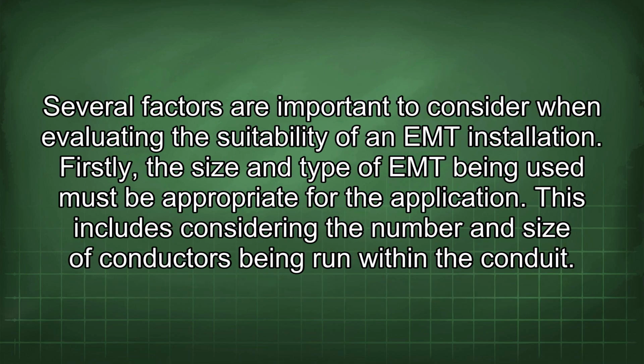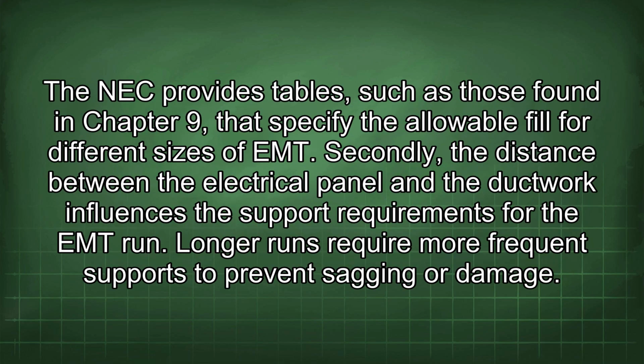Several factors are important to consider when evaluating the suitability of an EMT installation. Firstly, the size and type of EMT being used must be appropriate for the application. This includes considering the number and size of conductors being run within the conduit. The NEC provides tables, such as those found in Chapter 9, that specify the allowable fill for different sizes of EMT. Secondly, the distance between the electrical panel and the ductwork influences the support requirements for the EMT run. Longer runs require more frequent supports to prevent sagging or damage.